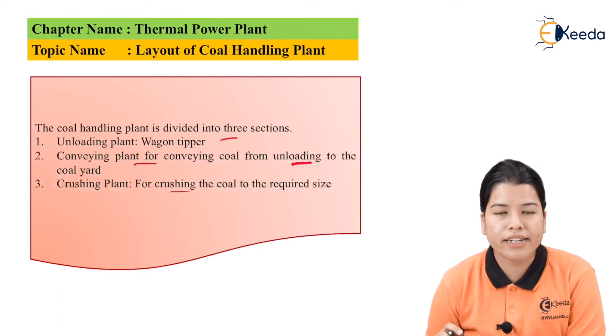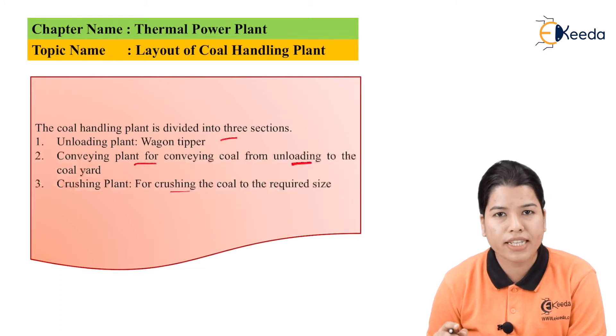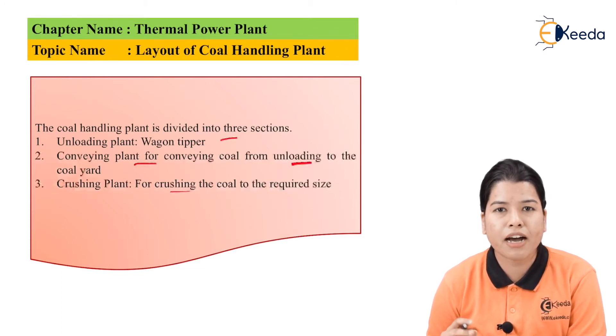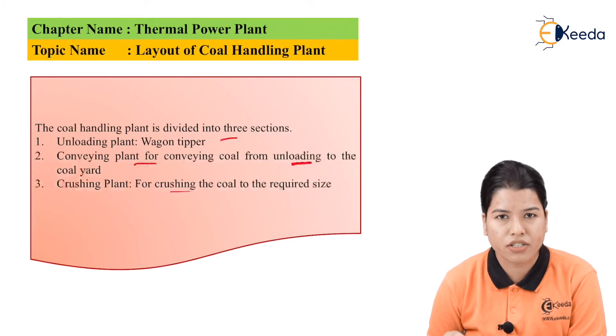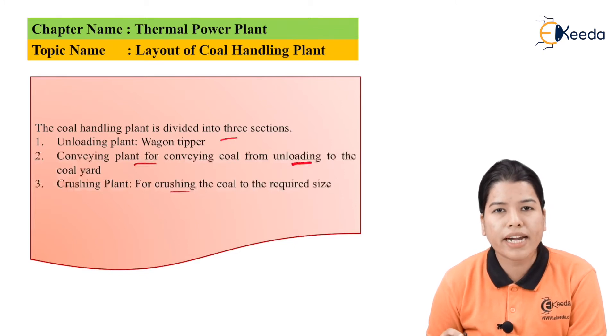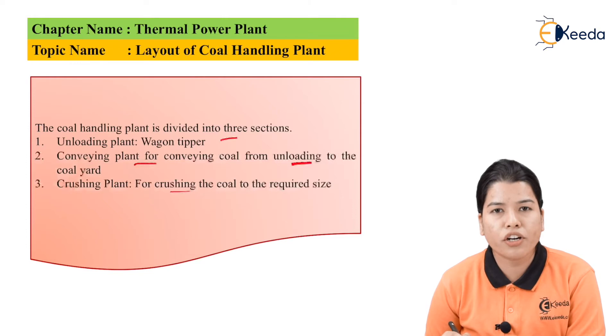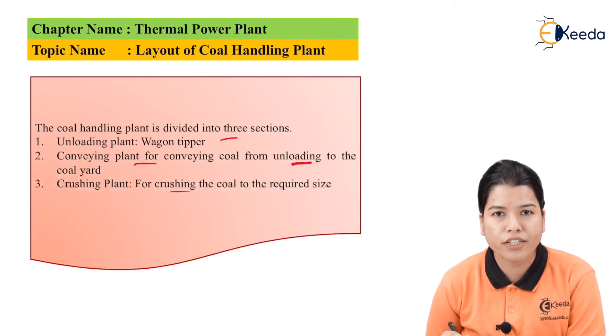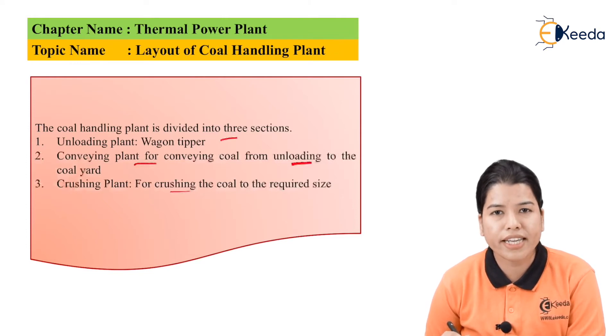The standard size for coal is required to be 19 mm or less than 19 mm. Coal with a size above 19 mm needs to be crushed. Since the coal available is not uniformly sized, in order to get the coal in the required size, crushing of coal needs to be done. Now let us see each of these sections in detail.